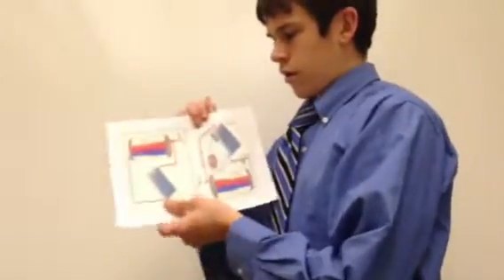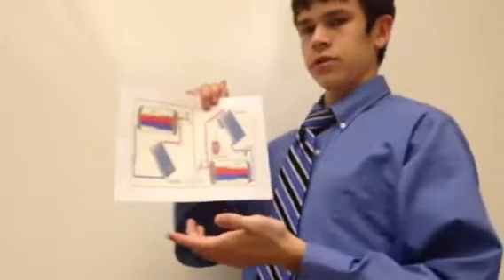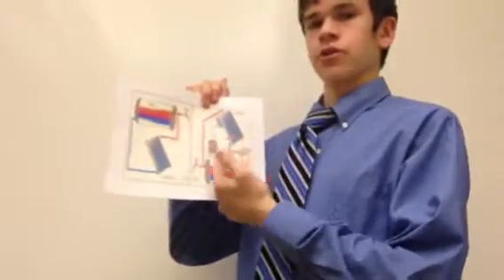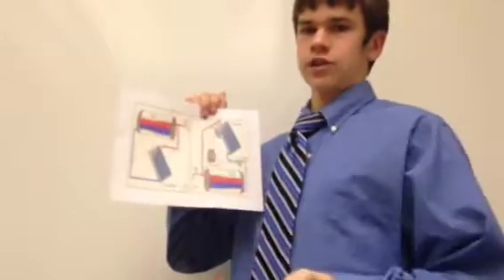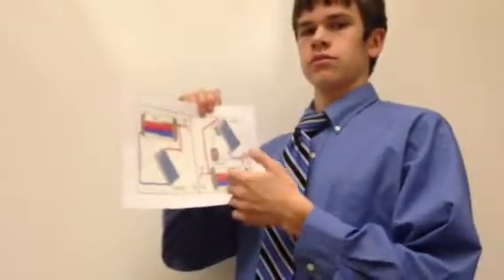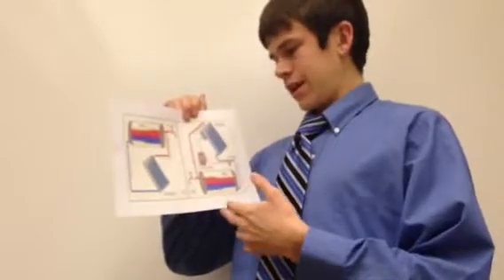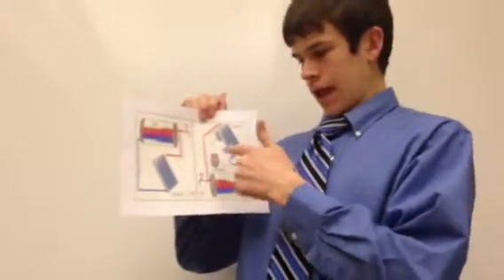Solar water heaters can be separated into two categories, which are an active and a passive system. An active system will use a pump to circulate the HTF throughout the system, whereas a passive system will use natural convection currents in order to provide the flow throughout the system. This can be seen here, where the passive system looks much more simple, and that is because there's no pump and there's no controller. It just relies on normal convection currents, and for this reason it is almost always cheaper than the active system. The active system, as you can see, has a pump and it has a controller.